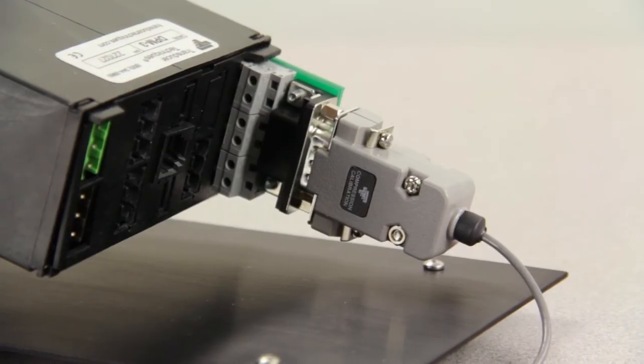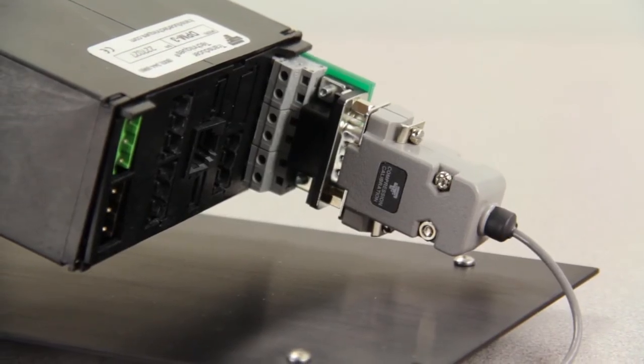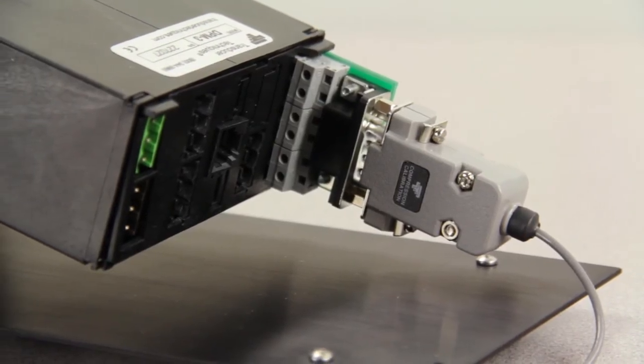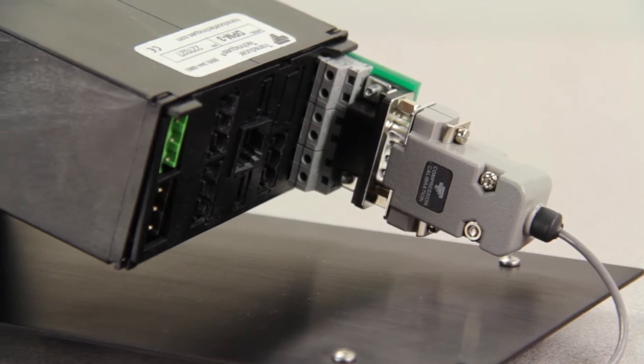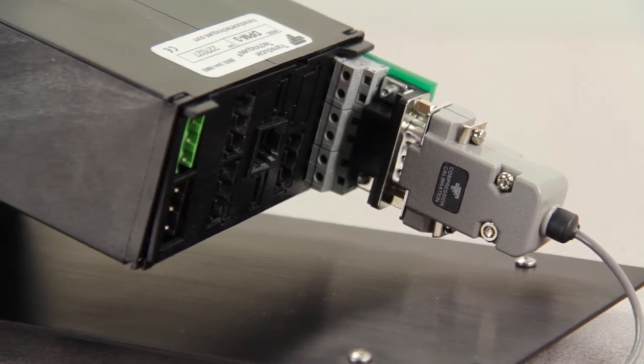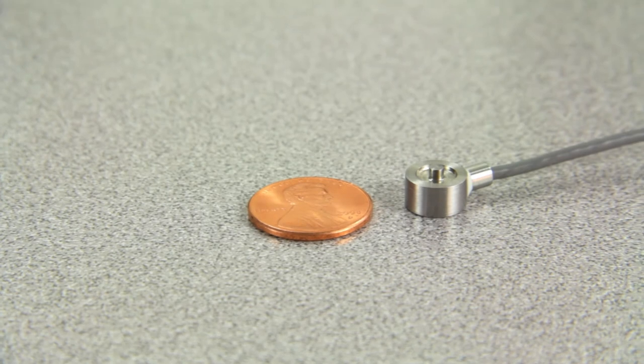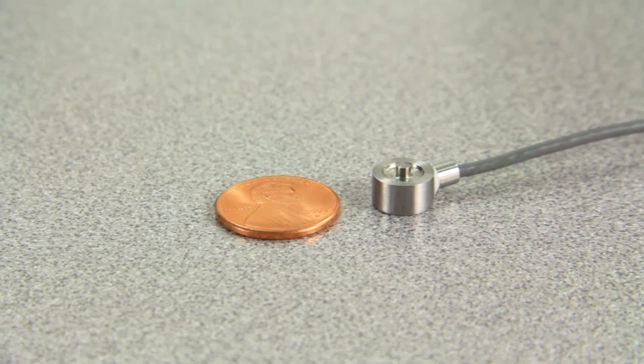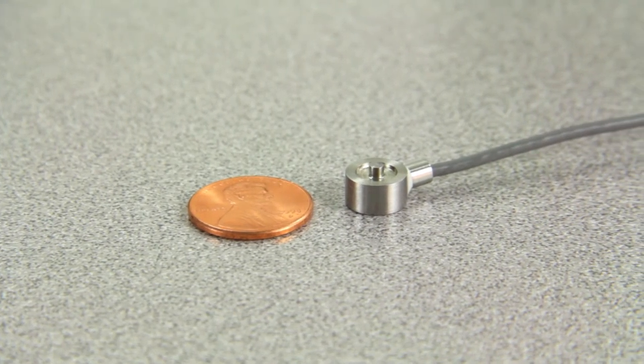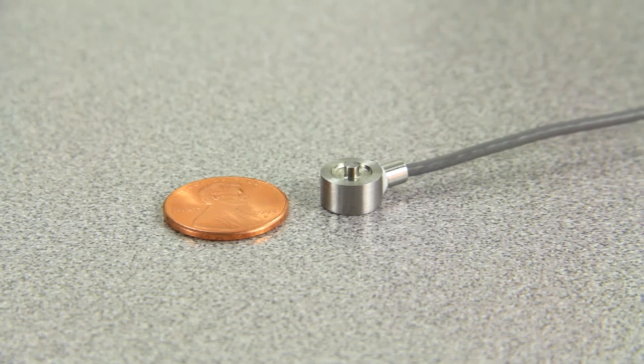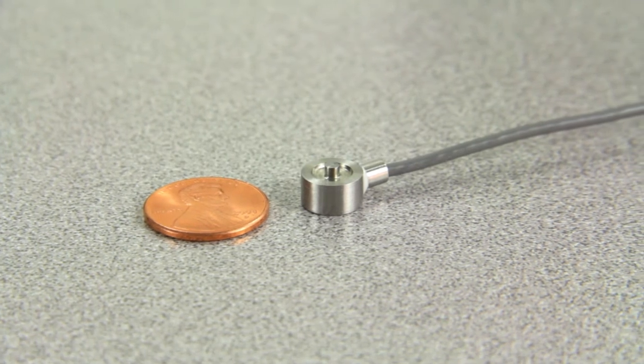Then it automatically adjusts the meter's excitation voltage for the sensor's appropriate value. This is to prevent an over-voltage. This is extremely important due to many miniature load cells have a maximum excitation of 5 volts, and most instruments supply 10 volts. The plug-and-play feature assures you won't over-voltage and damage your sensor.